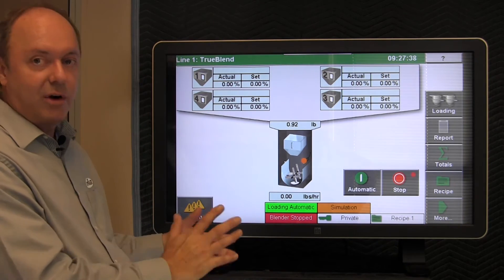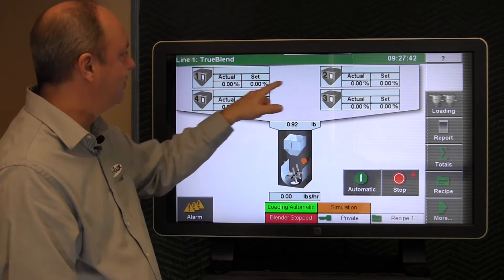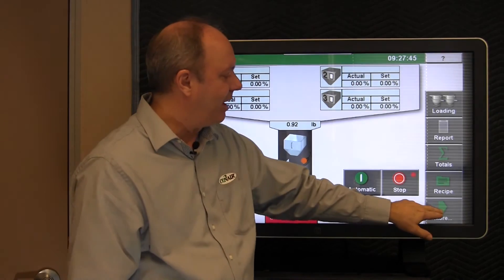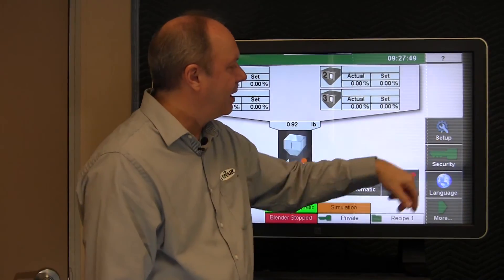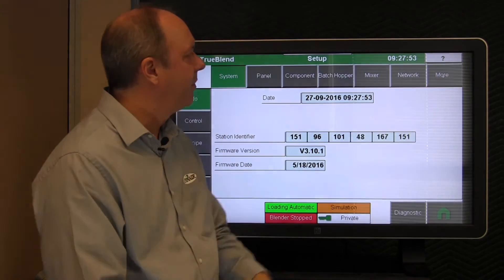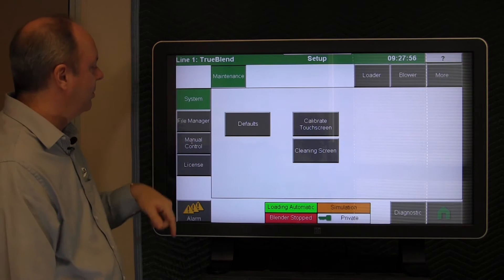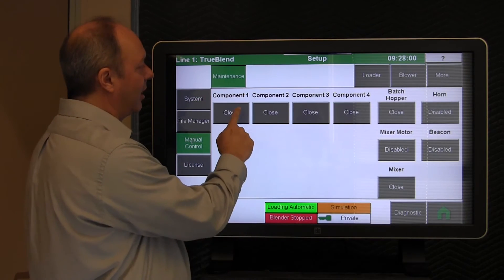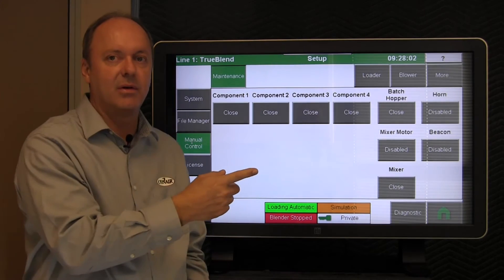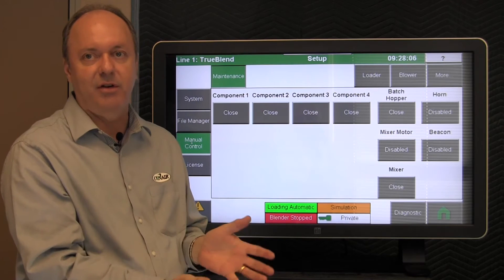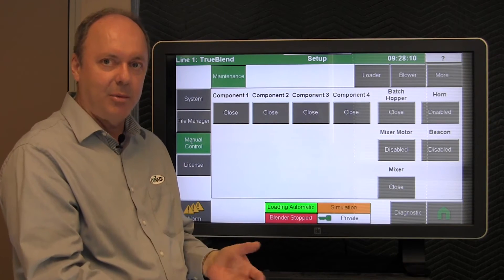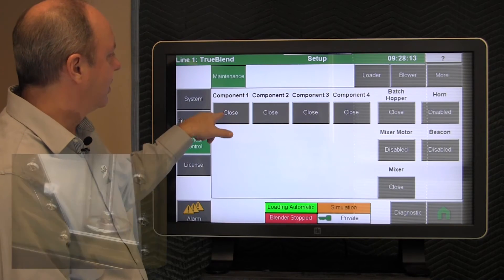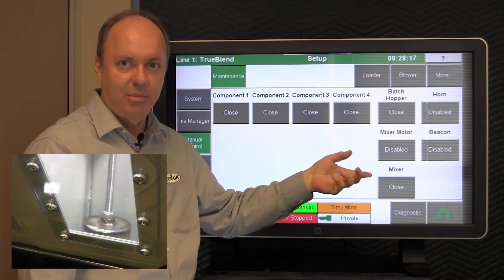So assuming you drained everything, in order to perform the manual tests of each of the components on the system, again we would navigate more here and setup and more. And then we tap manual control. Now, if you go into the screen and you start opening and closing valves while it's in auto, you will get a warning that says you have to stop the blender. That's why I warned you about it prior. We've actually stopped the blender, so we will not get that warning. But in this particular case, you can see that we have easy tap buttons for all the components within the blender.